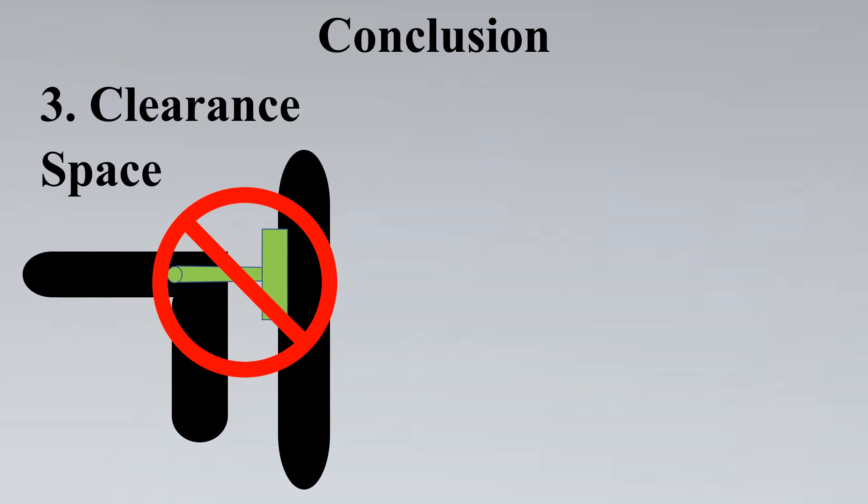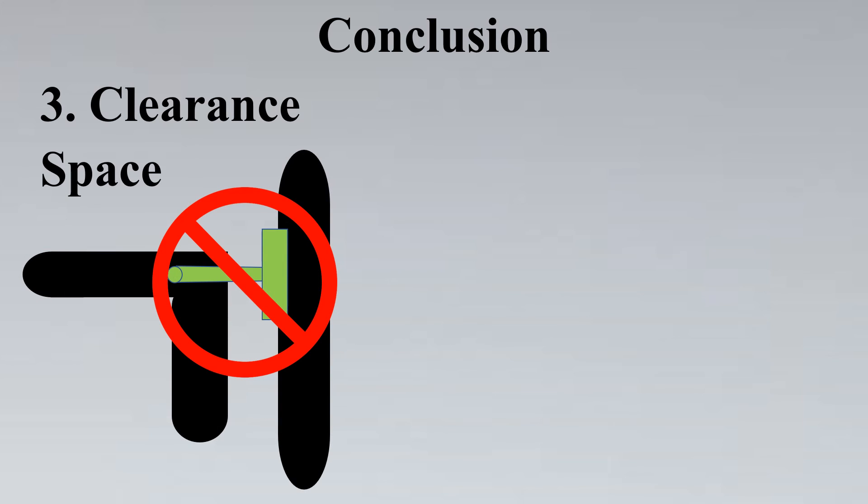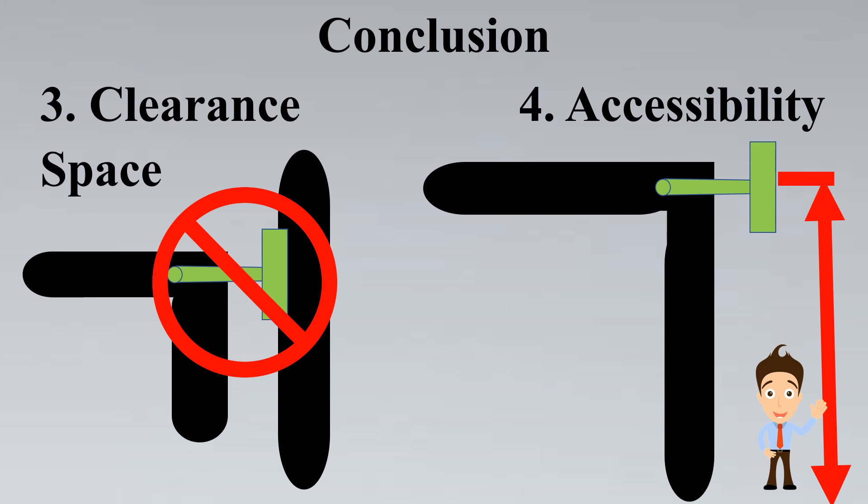The third criteria which we saw was the clearance space. We need to see that the space should be sufficient enough for the thermowell to be removed out of the process. We saw about API RP standard which says the clearance space should be the length of the thermowell plus 3 inches extra to it. Now the final criteria was the accessibility part of it. So we had seen that if a person needs to access it frequently then we need to take special permissions from the client or from the operations team that will such installations be feasible to them and how frequently they want to access the thermowell.